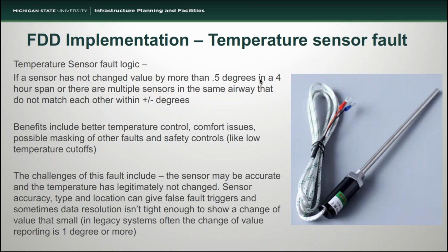Another relatively simple fault that we've put into place is a temperature sensor. And we're really looking for one of two conditions here. Either the sensor itself has changed less than half a degree over 4 hours, which likely indicates that it may have failed or it is not reporting correctly. Or if we have multiple air sensors that are in the same air path, the temperature should match within a degree or so as you go through. So if one or more of those sensors don't match, then that could indicate that there's a calibration issue with one or more of those sensors.